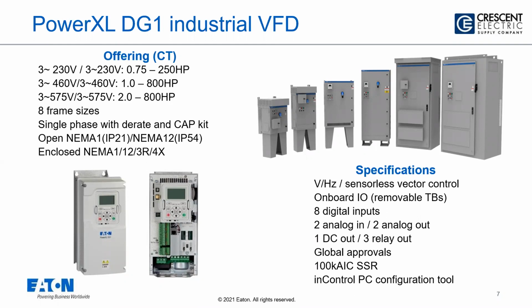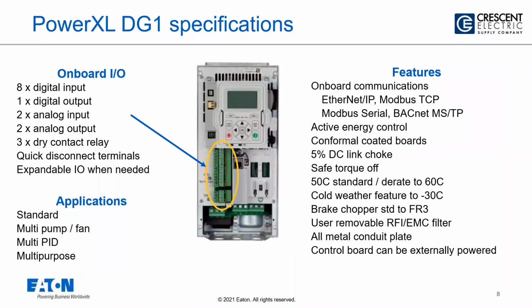So from a standpoint, we kind of talked about this. The terminal blocks are removable, which is nice, and they're keyed, so that makes it real easy from a service standpoint as well as just a troubleshooting standpoint. And we do have a removable EMC screw in it. So if you're going to go into like a high resistance ground or a corner grounded Delta system, you can now remove the EMC screw very easily. Just one screw to remove, and now it works on your IT system.